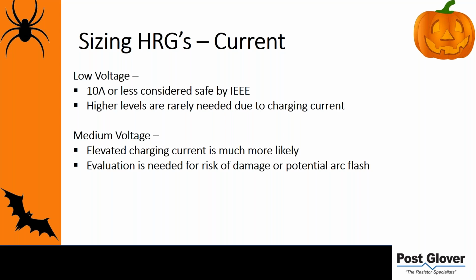I don't think there's a whole lot of division when it comes to 5 kV or below. It's typically fairly safe, but you need to worry about how often you're going to operate it and what kind of cabling you need. That's another ball of wax, but the point is you need to design properly. It can be done. When you get to higher voltages is where there's dispute on whether or not it's safe. I just wanted to bring that up.